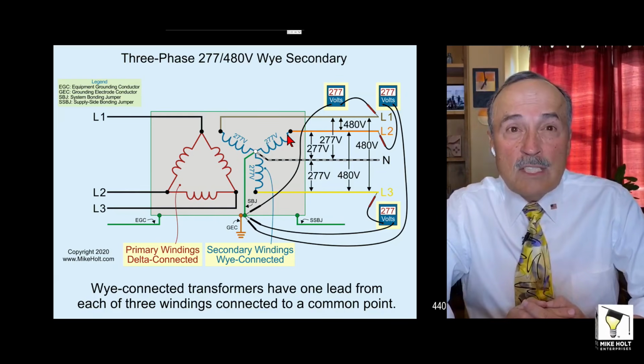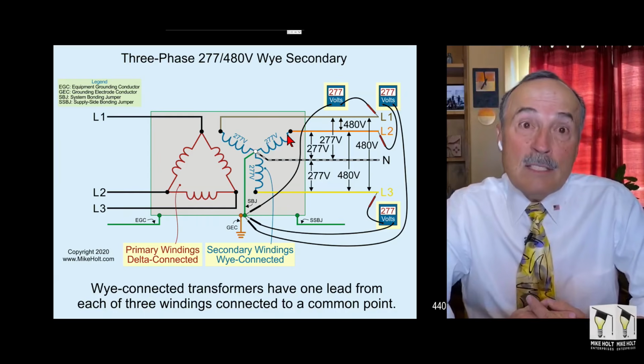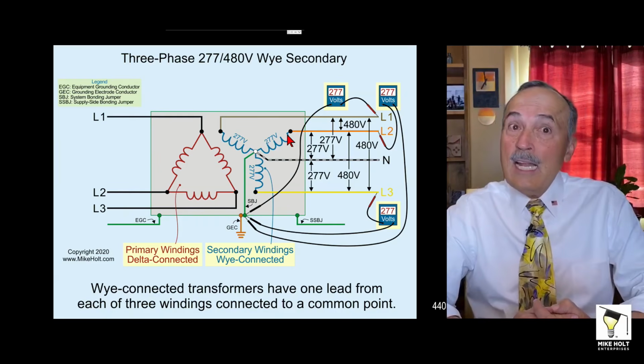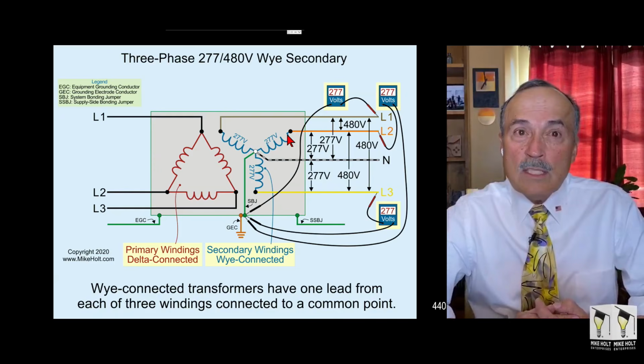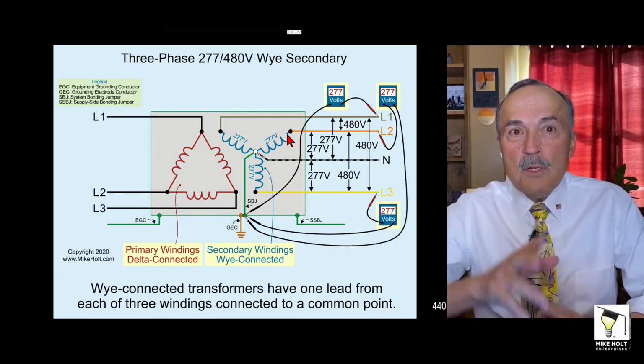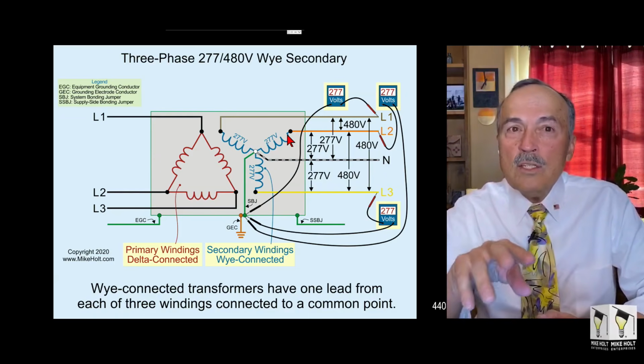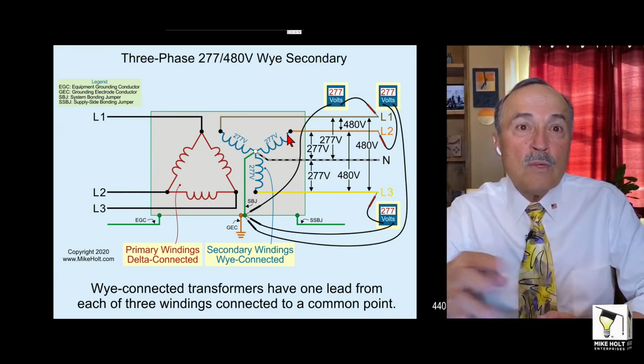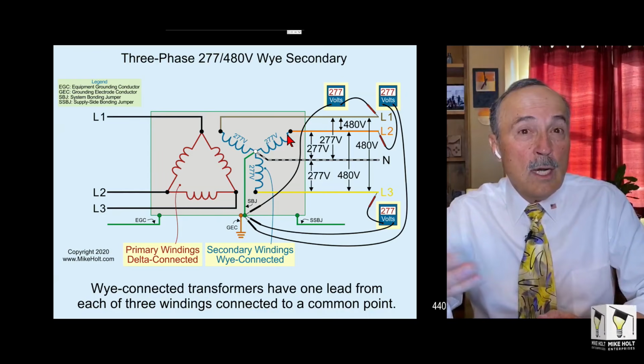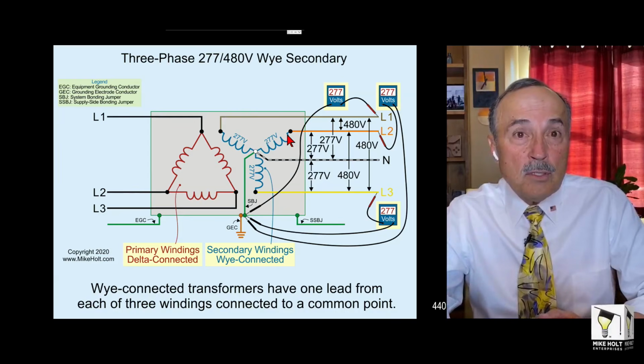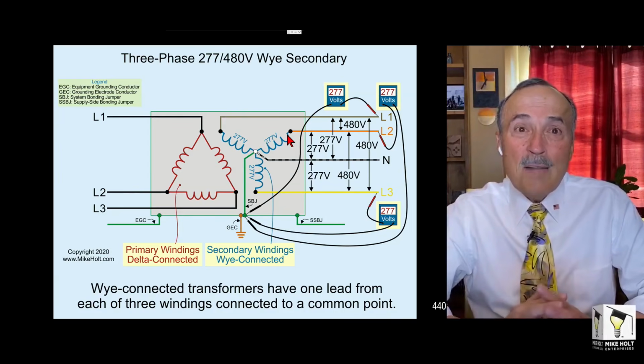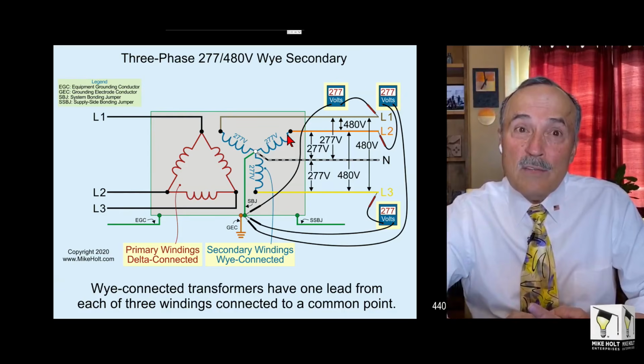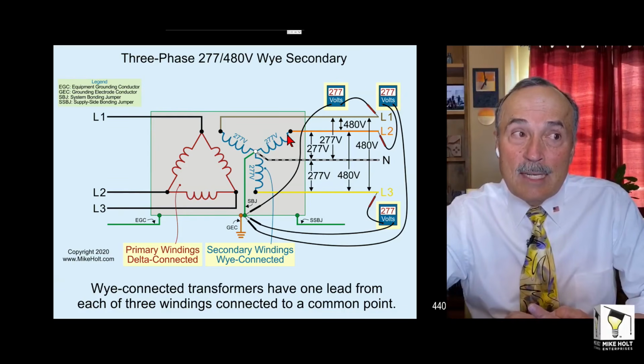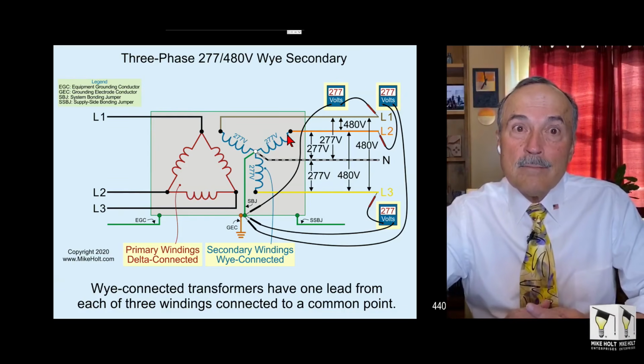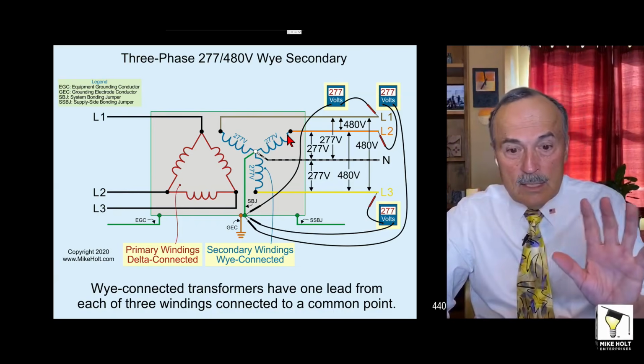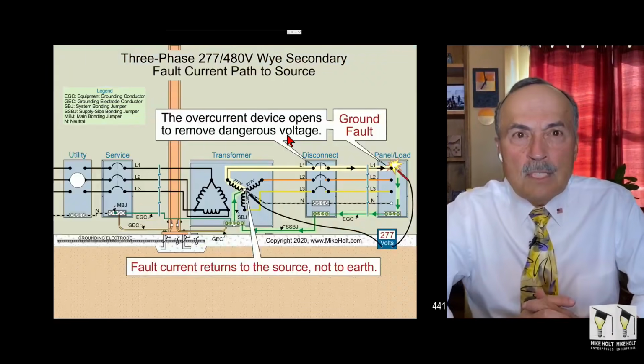When do you use 277/480? When the utility has it there, and you've got a lot of line and neutral loads, and you want some high voltages, and you're willing to put some transformers in to drop it down to 120/208 so you can pick up some receptacle loads and maybe some other lower voltage loads. But you're thinking, hey, I've got a school here. I'm not making a school 120/208, 3-phase, 4-wire. I'm going to make it 277/480. That's a designer's decision.